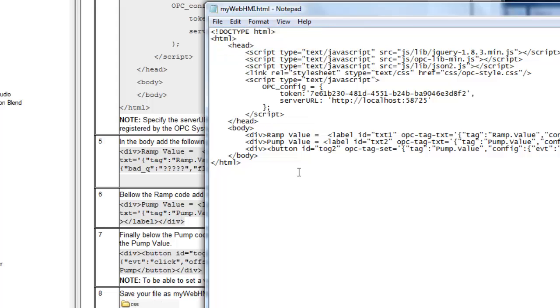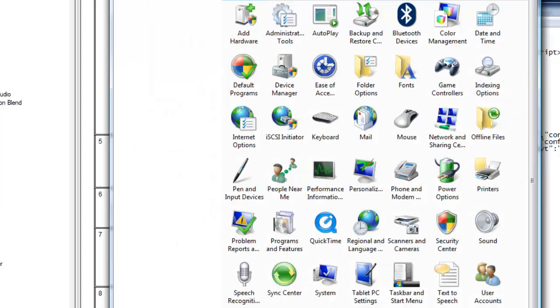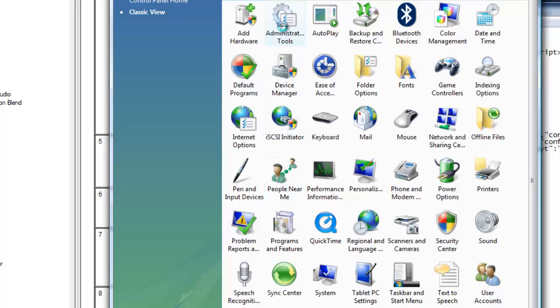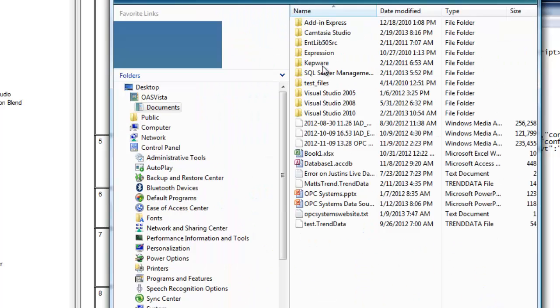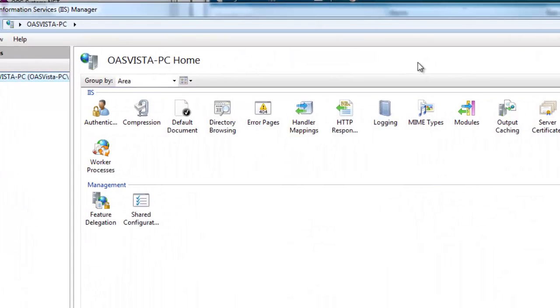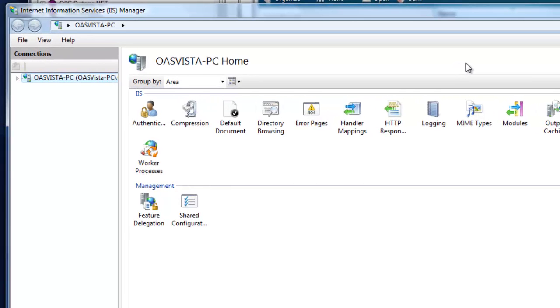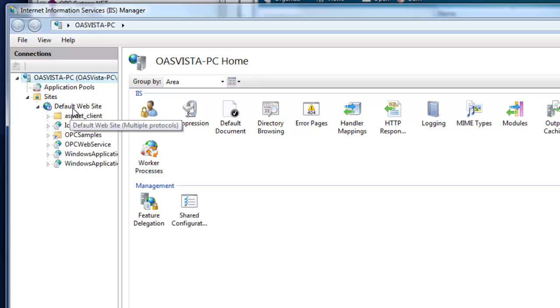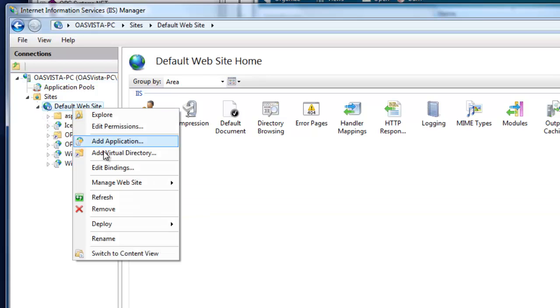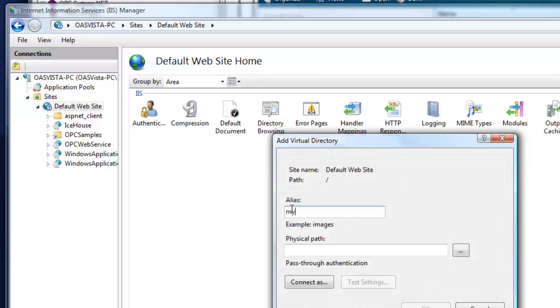Now we'll save our file, and now we'll use IIS to create a virtual directory pointed to that project directory. That's typically found under administrative tools, and there you see internet information services. If you don't see internet information services, go to add remove programs, and there you'll turn on and off windows components, and then you'll see IIS to turn that on. Under your default website, you'll right click and select to add a virtual directory. Choose any alias name you like. Again, I'm going to choose mywebhmi.